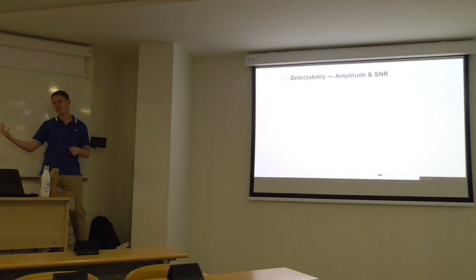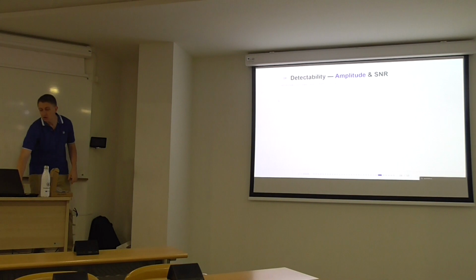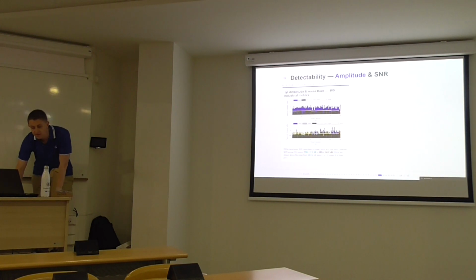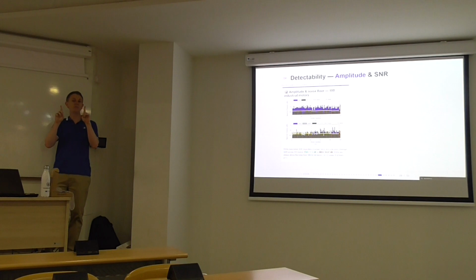And the same with the mixed eccentricity harmonic. So those are the results. Here in the upper figure, blue bars are the rotor load harmonics amplitude and black bars the noise floor. Here in the bottom figure, we have the same but for mixed eccentricity harmonic. So we have two main mixed eccentricity harmonics.